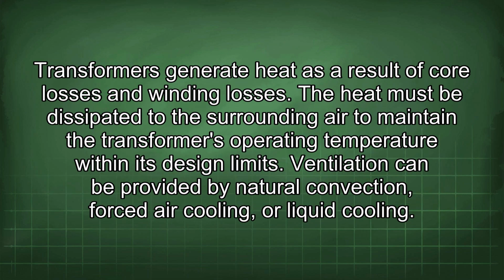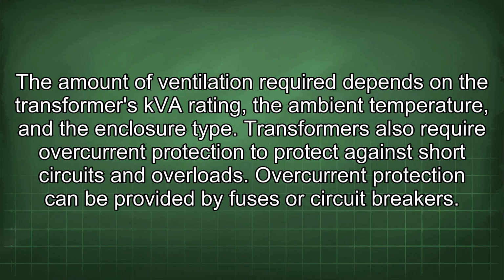Transformers generate heat as a result of core losses and winding losses. The heat must be dissipated to the surrounding air to maintain the transformer's operating temperature within its design limits. Ventilation can be provided by natural convection, forced air cooling, or liquid cooling. The amount of ventilation required depends on the transformer's kVA rating, the ambient temperature, and the enclosure type.